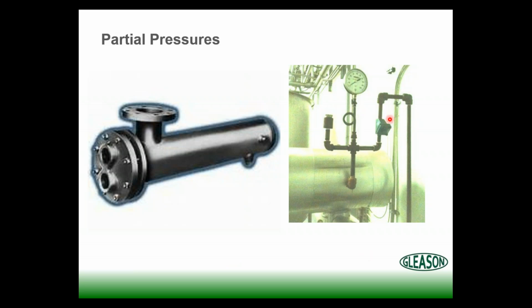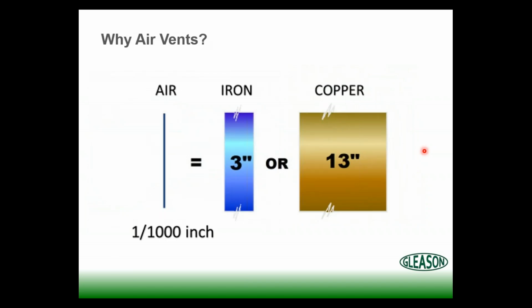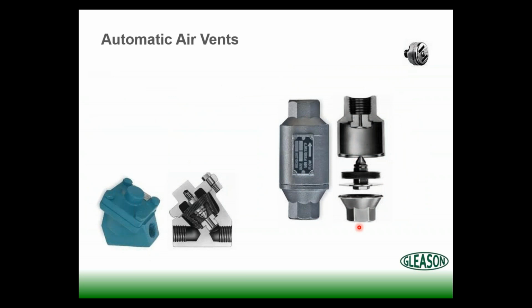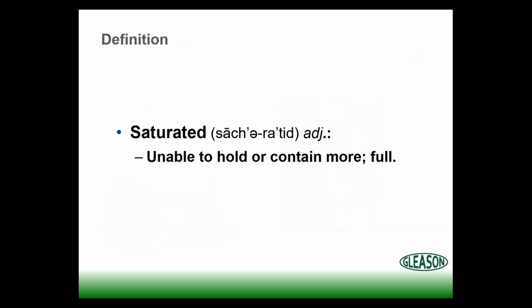Here's our vacuum breaker, air vent. Let's have an air vent, because if we don't, we've got to push all that air out through the steam traps, and they're not very good at that, only as a secondary means. Air is quite an insulator: 1/1000th of an inch has the same insulating properties as about 13 inches of copper. So we want to use these automatic air vents on all of our heat exchangers. Real quick definition here, the term saturated means unable to hold or contain more, it's full.